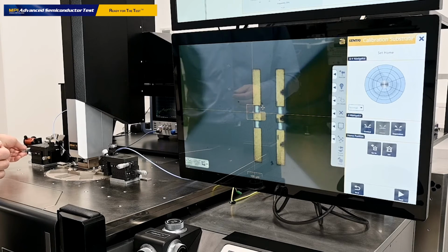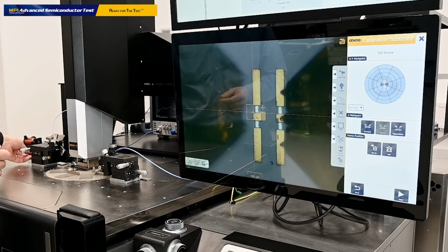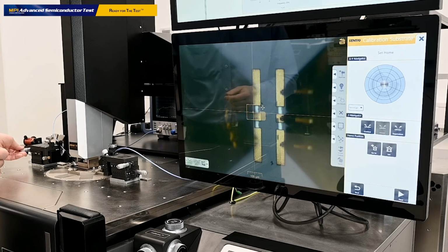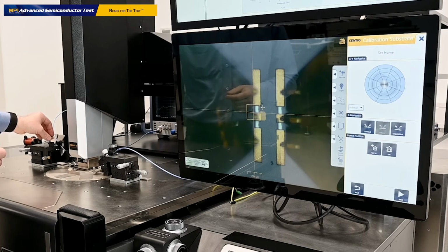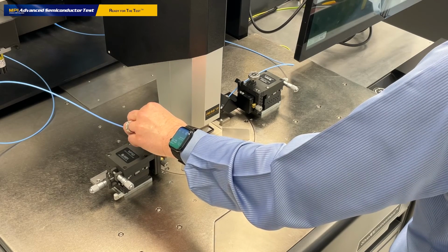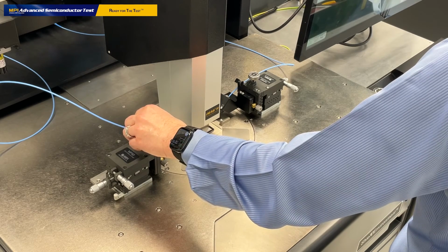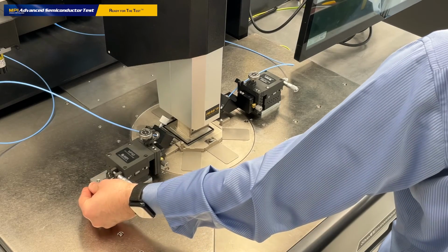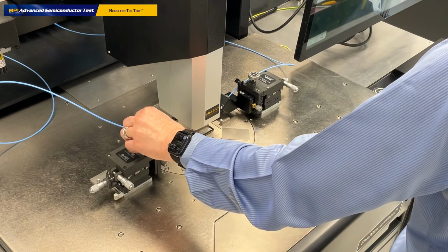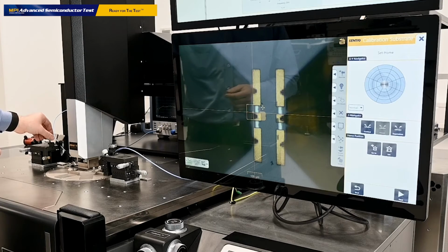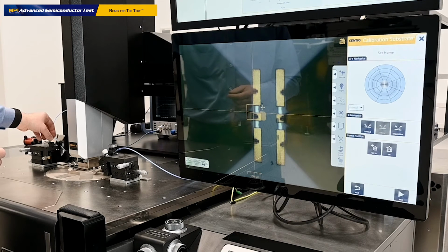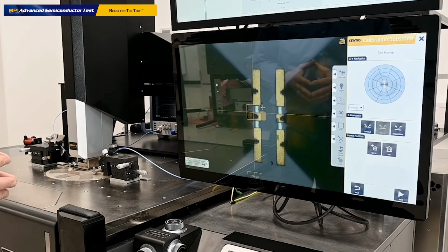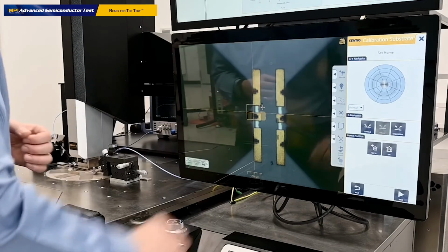So let me repeat a similar exercise for the port 1 probe. Bring it to the focus, adjustment in X and Y. Bring to the Z. So getting very close. We want to bring probes to the middle of the standard pad and make sure that we have an overtravel of about 5 micron. Yeah, the probe starts slightly moving. So this is enough, and this is the good probe adjustment. So we set up local home.